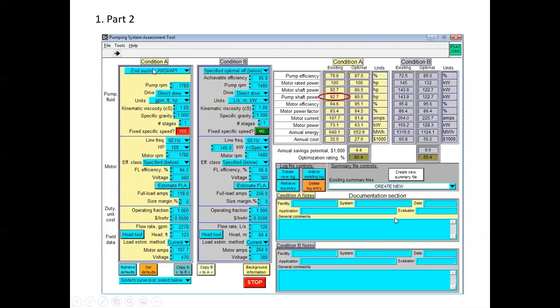End suction ANSI API pump. This is the pump data, 1180. I'm sorry, 1780. Brain's not working. It's direct drive. We don't know anything about a belt drive. Units, standard water, 1 stage. Yes, for the optimal, we're going to stay within the same type of pump. Frequency 60 hertz, 100 horsepower, 1780 RPM.